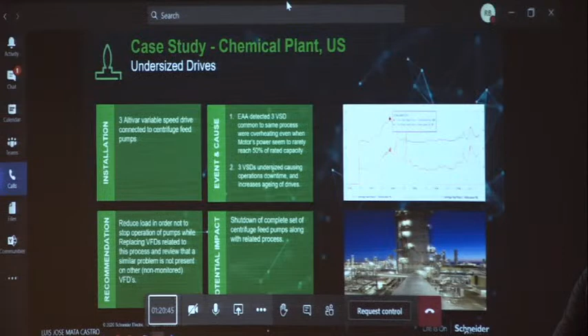By having the real-time information on how these variable speed drives were performing, our service engineers detected that there was overheating happening in some of the motors. But the strangest thing was that these motors were overheating without having reached even 50% of the rated capacity. So this was an alarm that was automatically raised to our service bureau, and we, of course, contacted the customer to try to identify the root cause of this situation.